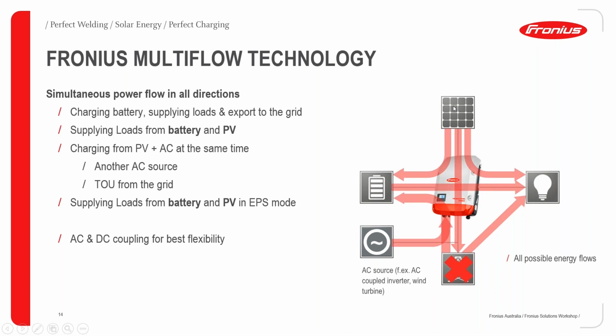Also, when you're charging, you can charge from PV, or if you want to top it up from any other AC source, you can do that, and it will then charge with AC and DC at the same time. You can do it with time of use. So let's say you want to set up maximum minimum charge rates from the grid, or if you're in off-peak tariffs or various tariffs, you can charge the battery at a lower tariff if you like, and then use it to discharge at a higher one. That gives you those kinds of possibilities.